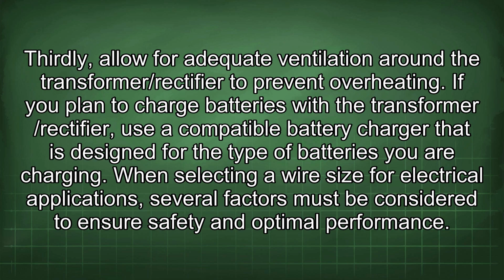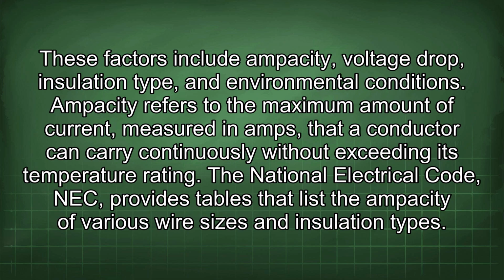When selecting a wire size for electrical applications, several factors must be considered to ensure safety and optimal performance. These factors include ampacity, voltage drop, insulation type, and environmental conditions. Ampacity refers to the maximum amount of current, measured in amps, that a conductor can carry continuously without exceeding its temperature rating. The National Electrical Code, NEC, provides tables that list the ampacity of various wire sizes and insulation types.